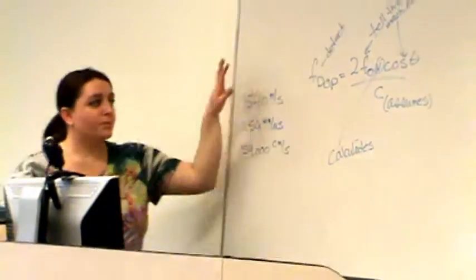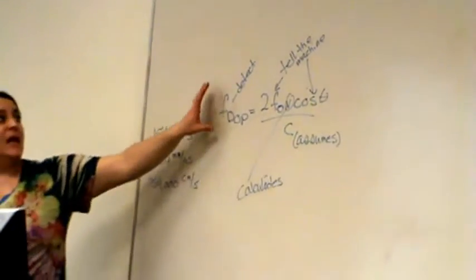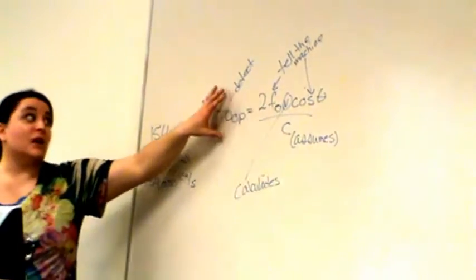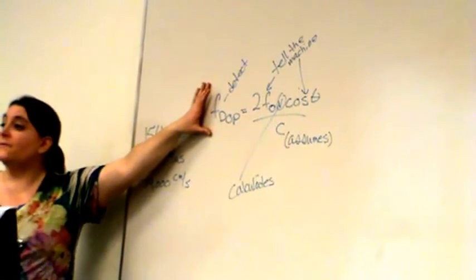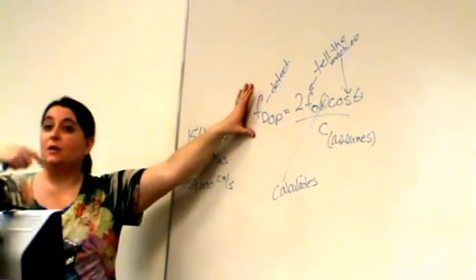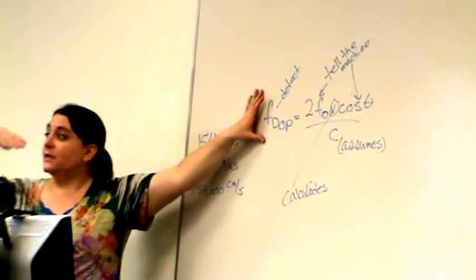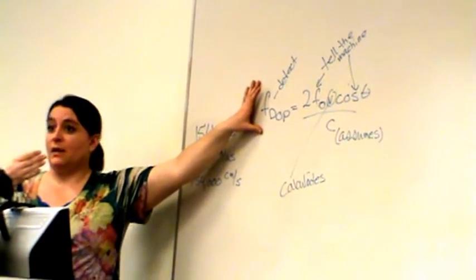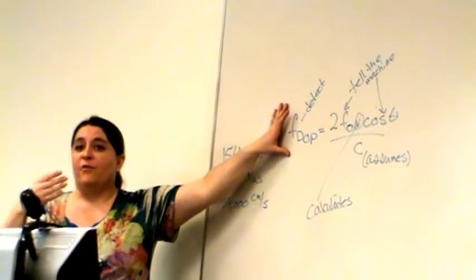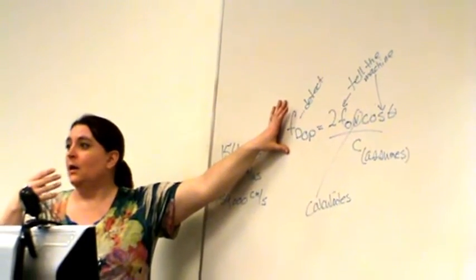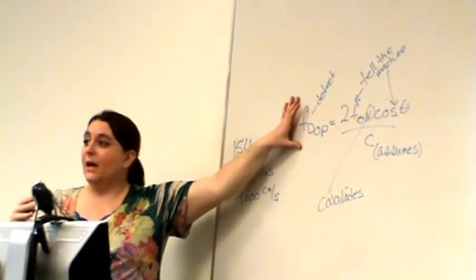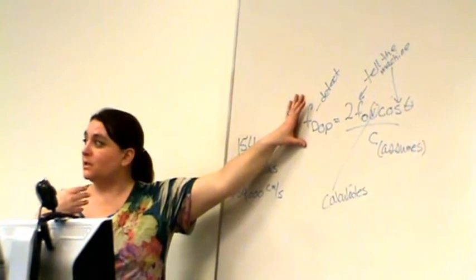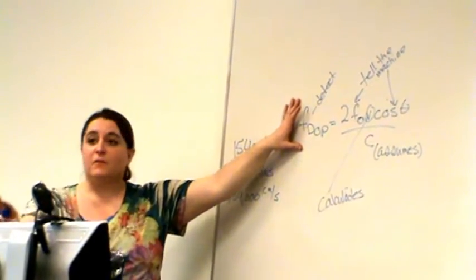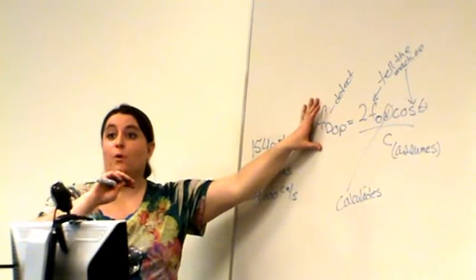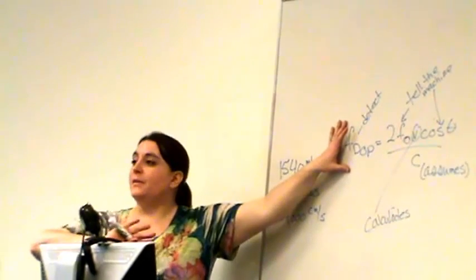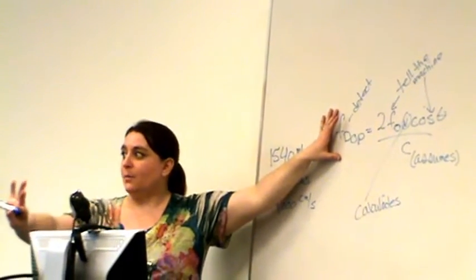It assumes 1540. It knows what it sent in, so then a shift comes back out. Remember, we sent in 5 megahertz, but what we get out might be a little higher or a little lower. If it's a little higher, that means the motion was towards us. If I got back out 5.003 megahertz when I sent in 5, that means motion was towards me. It was a positive Doppler shift. If I sent in 5 megahertz and got back out 4.997, that meant the motion was away from me. I had a negative Doppler shift.